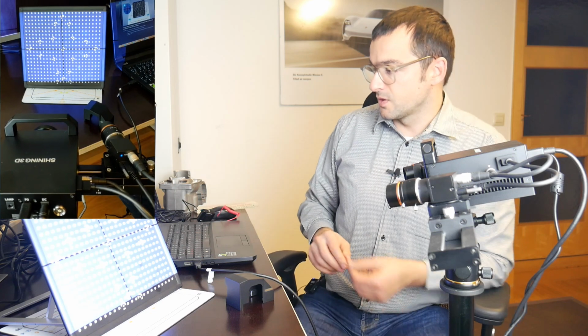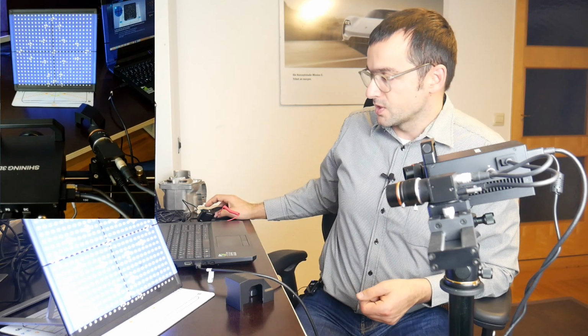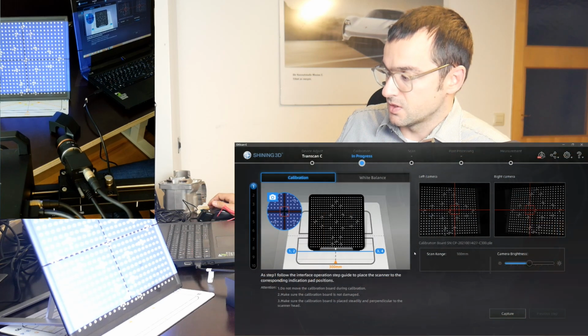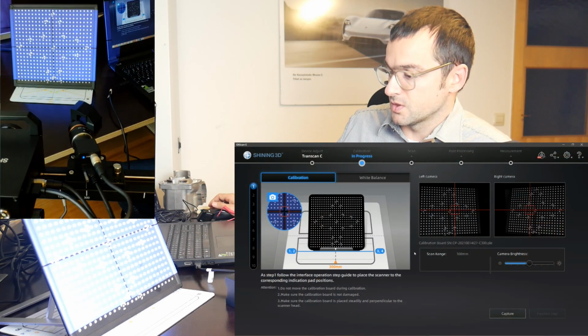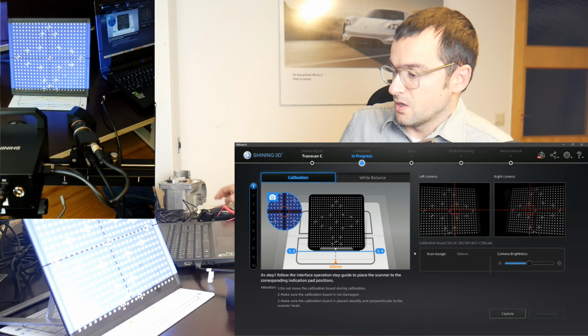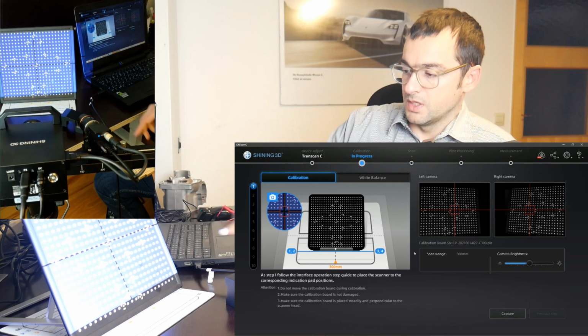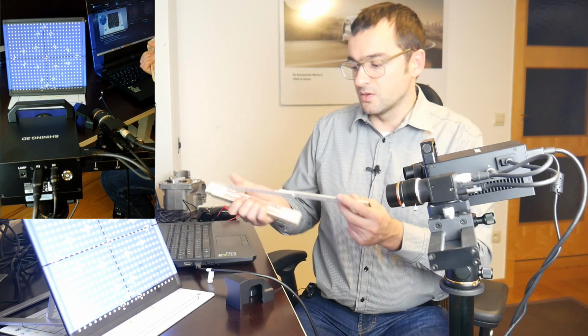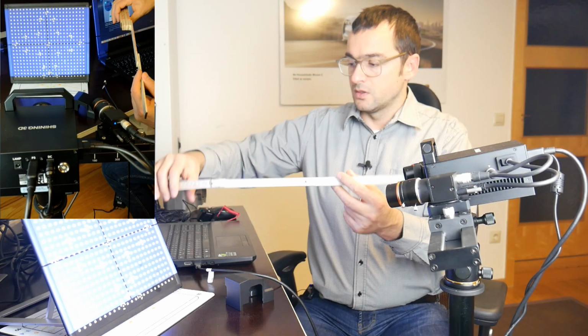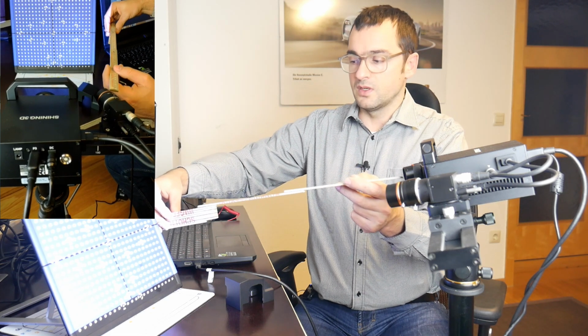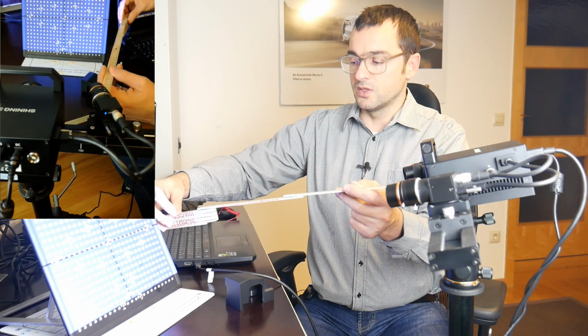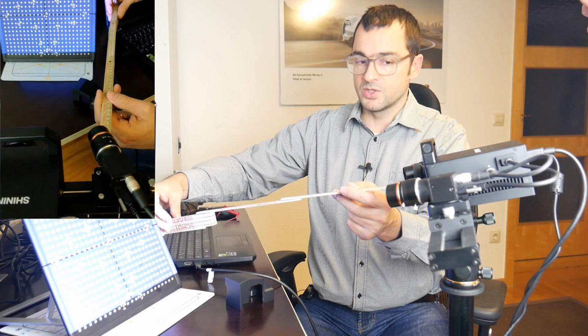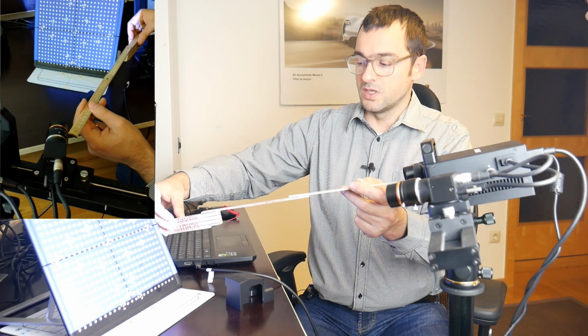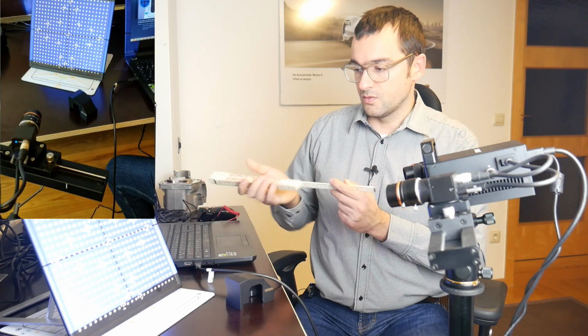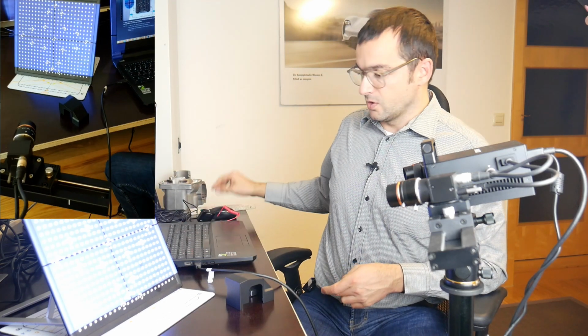The next thing I have to ensure is that the projector is centered with the camera centers, and as they are matching on the middle of the calibration board at an angle, it's important that they do that at the right distance. So using the manual, it will tell you something about 470 millimeters distance from the calibration board to the optical unit, more or less. So this is fine. I could go even a bit nearer.